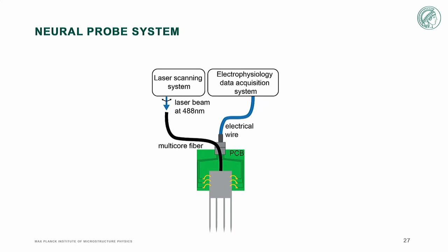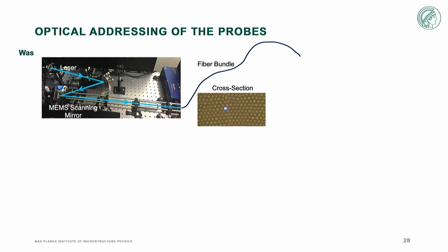First, the optical addressing. This is our setup back in Toronto. The way we do addressing on the probe is to keep most of it off the probe chip. Before, we had this optical table long system where laser light comes in and hits a MEMS scanning mirror like this, then the light is coupled into a Fujikura fiber bundle, a commercially available fiber bundle. By scanning the mirror, you can address different cores in this imaging fiber bundle.